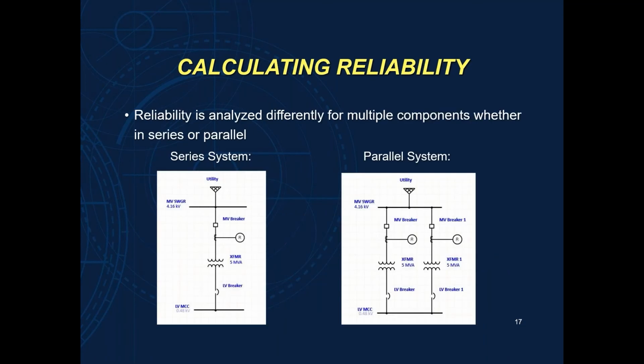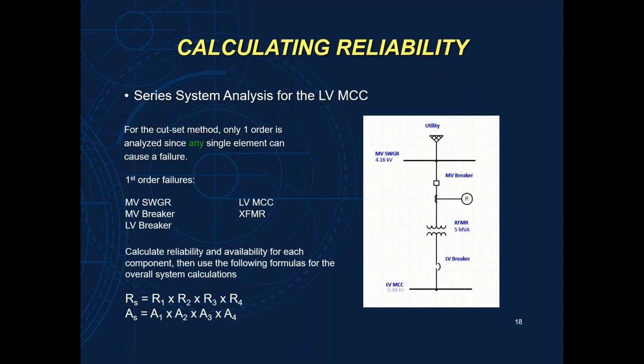So we're going to look at a couple different examples here just to compare a series system, which is a single fed radial system shown on the left, and a parallel system on the right, keeping in mind that for the purposes of this example, this is a fully redundant supply, meaning on the right in the parallel system, the MCC loads only require one of those two transformer feeders in order to operate. So when we want to do the series system, we're going to do the cut set method. We only need one order here. We're not going to have a second order cut set because if any one of these components fails, we lose our system. Okay, so this is a very straightforward calculation.